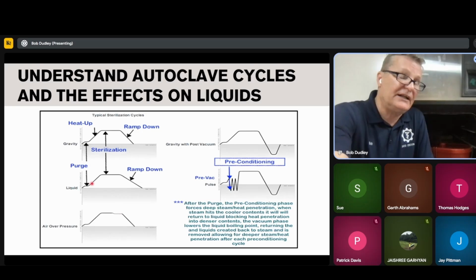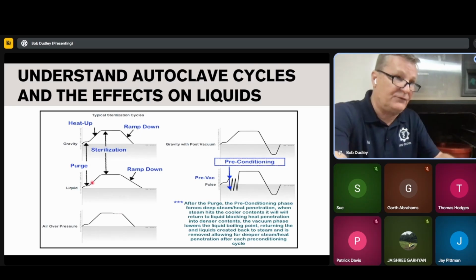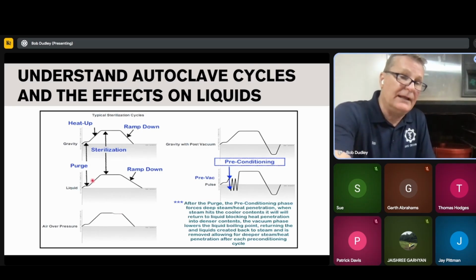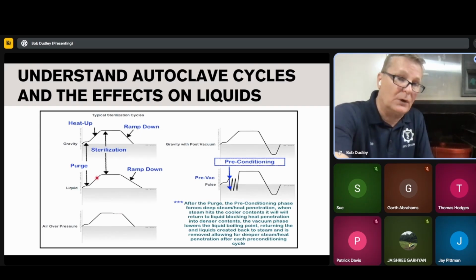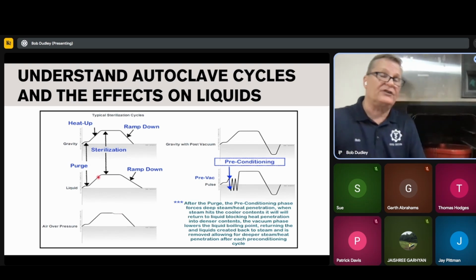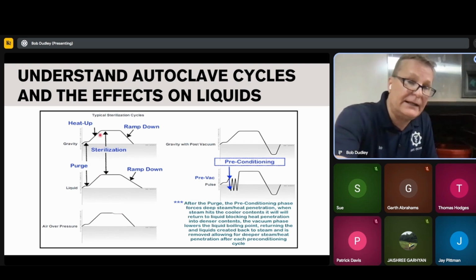So it may sit here after 2 or 3, and it's going to pump it in, and it's going to go, okay, did we achieve the pressure? Is the temperature staying there? Is there too much drop? Now we're going to pump in another 2 or 3 more, and another 2 or 3 more, until it gets to the point. So if your sterilization, which is this line, is 121 or 15 psi, it's going to get to the very last check before it gets to sterilization right here and right here.